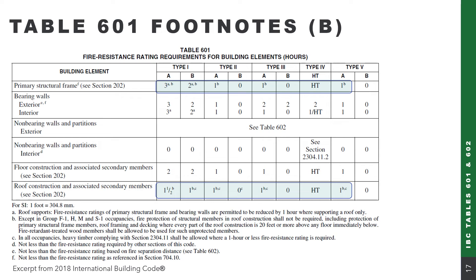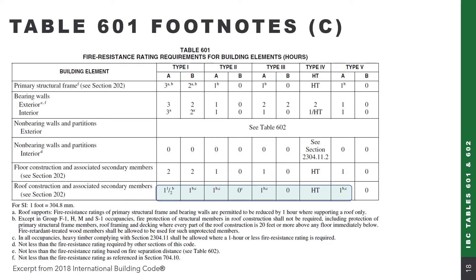Footnote B provides guidance that if the roof structure is 20 feet or more above the floor below, there is an opportunity to eliminate the fire protection requirements for those members. Footnote C is related to roof construction and allows a heavy timber roof system to be used in lieu of a one-hour rated roof construction, with the rationale that heavy timber's thick, solid wood members provide inherent fire endurance very similar to a typical one-hour rated assembly.